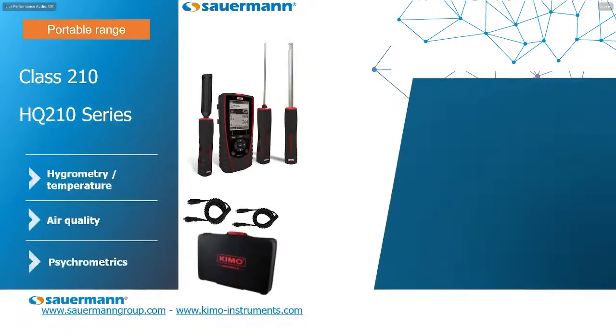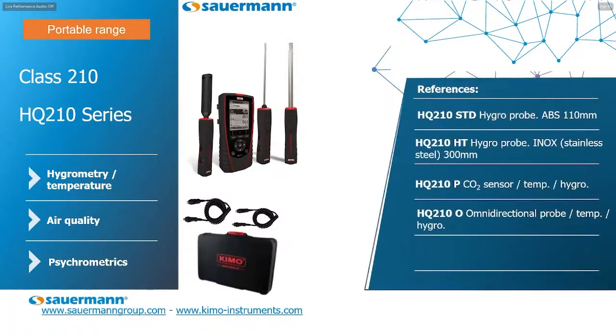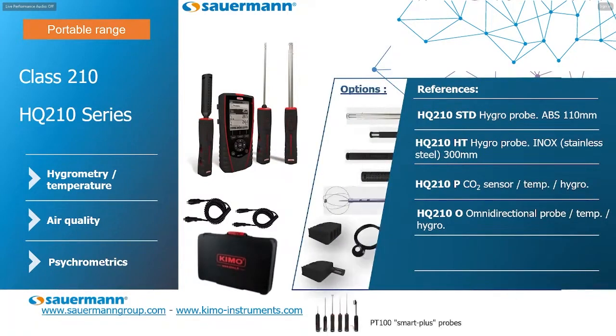Then the next step up is our Class 210 instruments. The key one I want to point out here, once again, is our HQ 210. Now we're getting into some other parameters. This one specializes more as what we call a thermal hygrometer, which is the psychrometrics. So here you're measuring air temperature, the temperature within the room or the building, and also obviously the hygrometry, which is the relative humidity. With these models, you can see we have a few different kits here. We have the first one listed as a standard kit, where you get measurements for temperature and humidity. Once again, the key here is they're quick and easy measurements, but reliable and accurate.